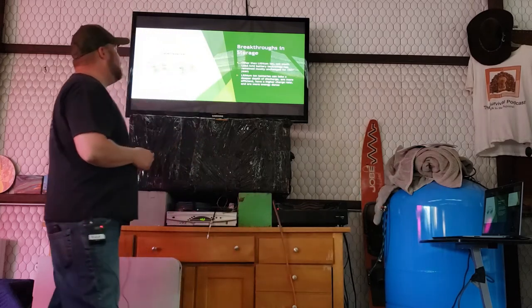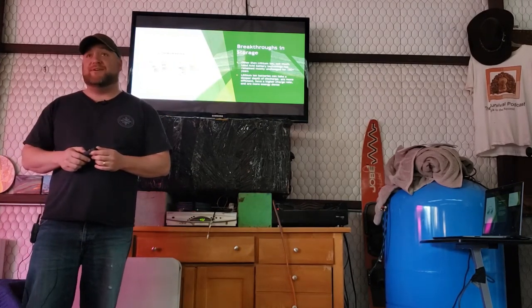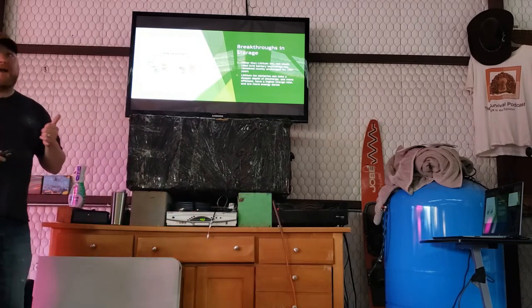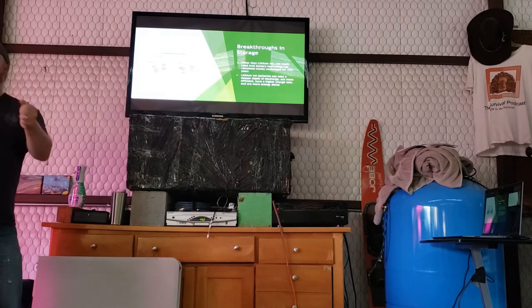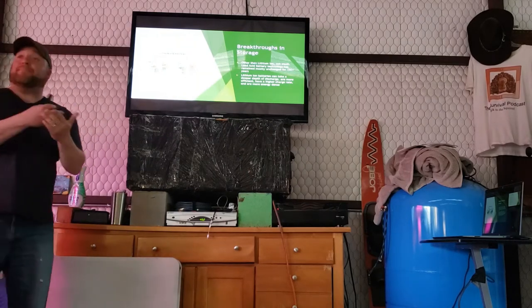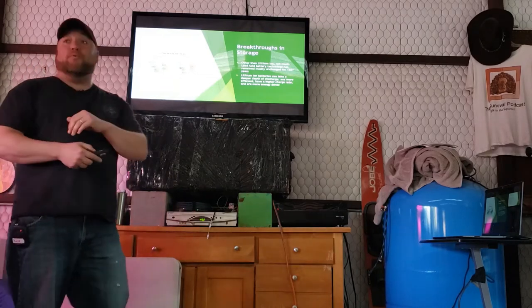So let's talk a little bit about breakthroughs in storage. Really, other than lithium ion, not much. I mean, flooded lead acid batteries really haven't changed in about the past 150 years. So lithium ion, when it came out, that was a big jump forward. Now, lithium ion batteries can take a deeper depth of discharge, which means you can take more of the stored energy out of them without damaging them than lead acid batteries. They're more efficient. They have a higher charge rate, which means you can top them off faster.